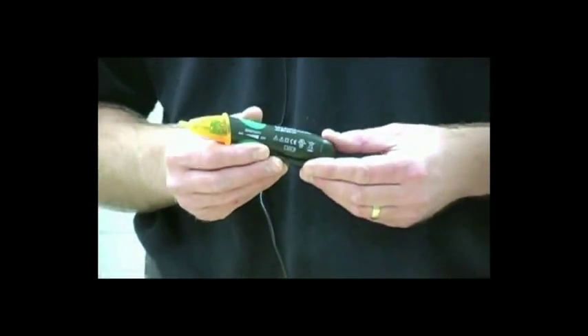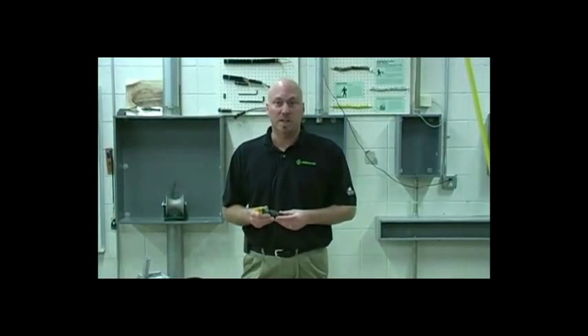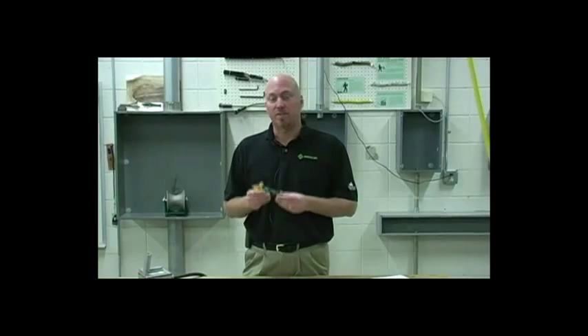The GT16 is a Category 4, 1000 volt rated tester with adjustable sensitivity. Its range is from 5 volts all the way up to 1000 volts. It signals the user of the presence of AC voltage through intermittent beeps and flashing LEDs.